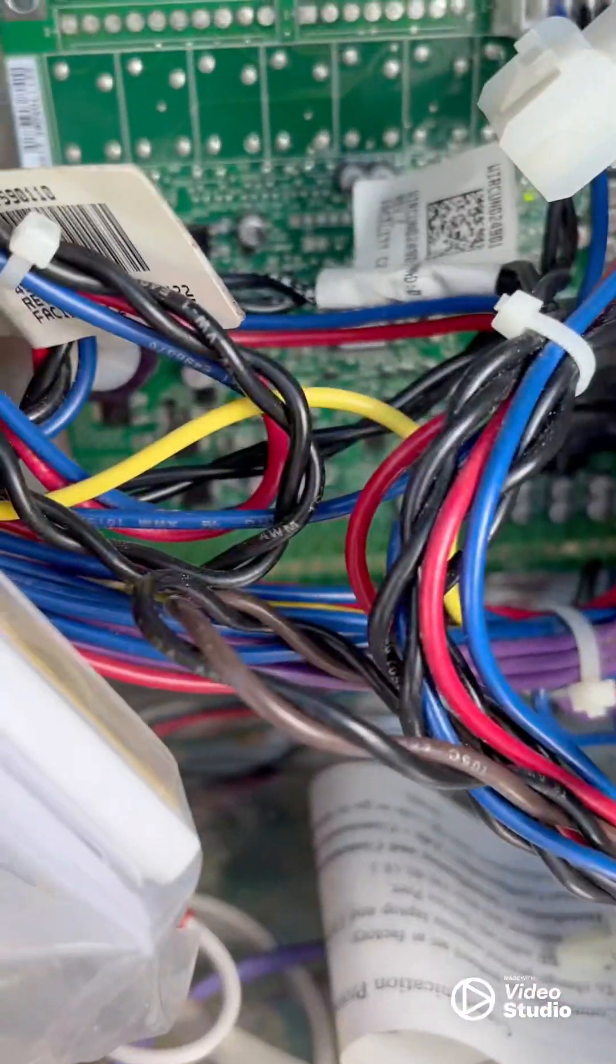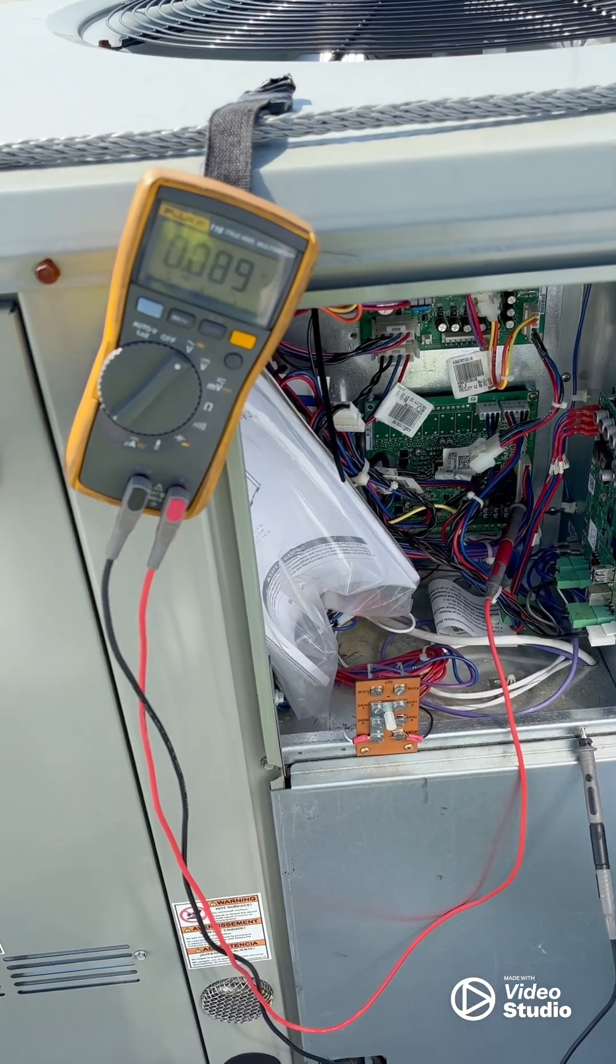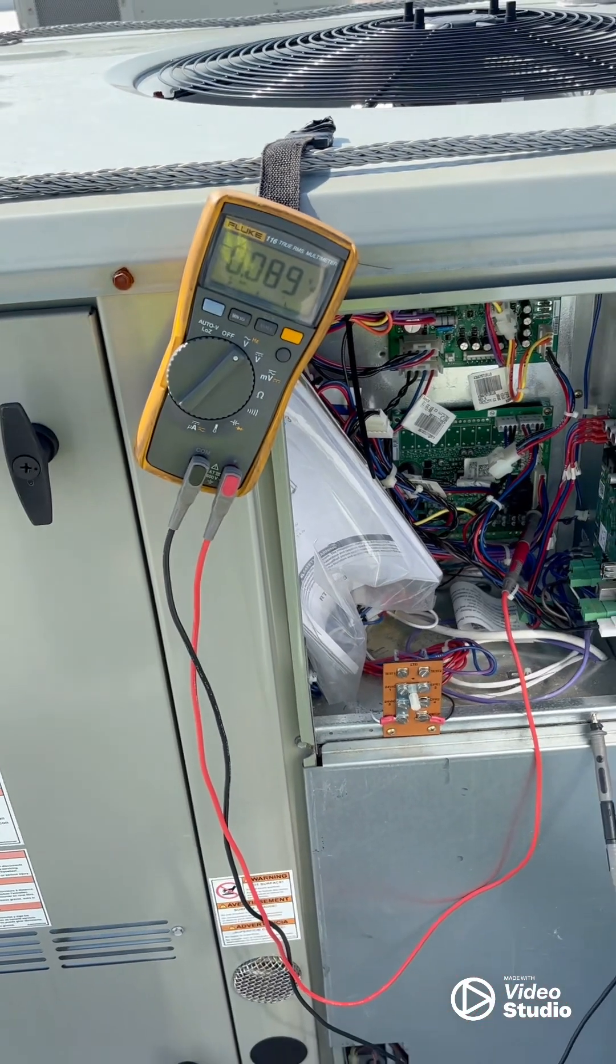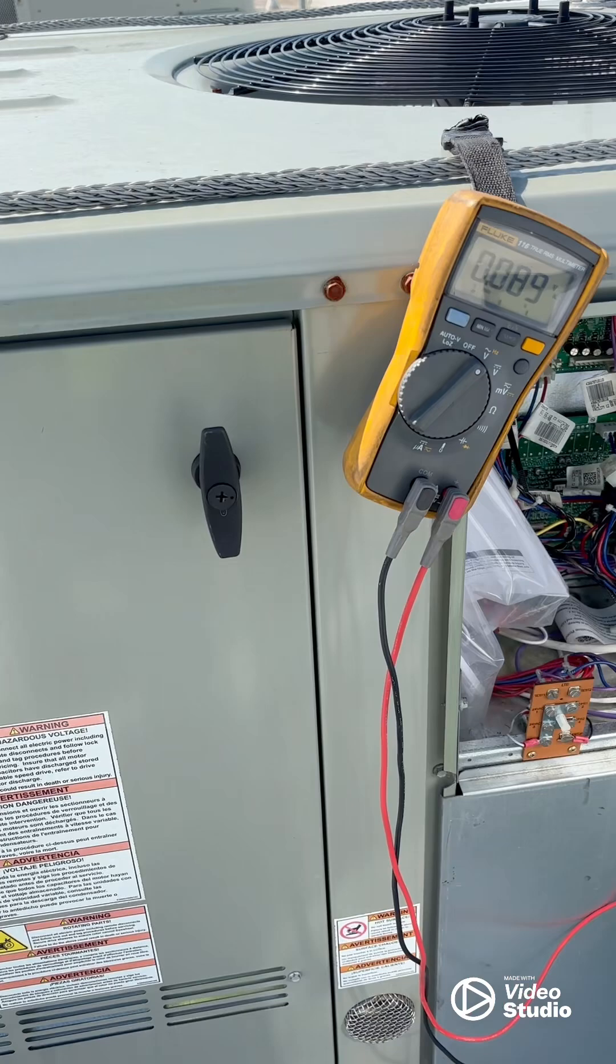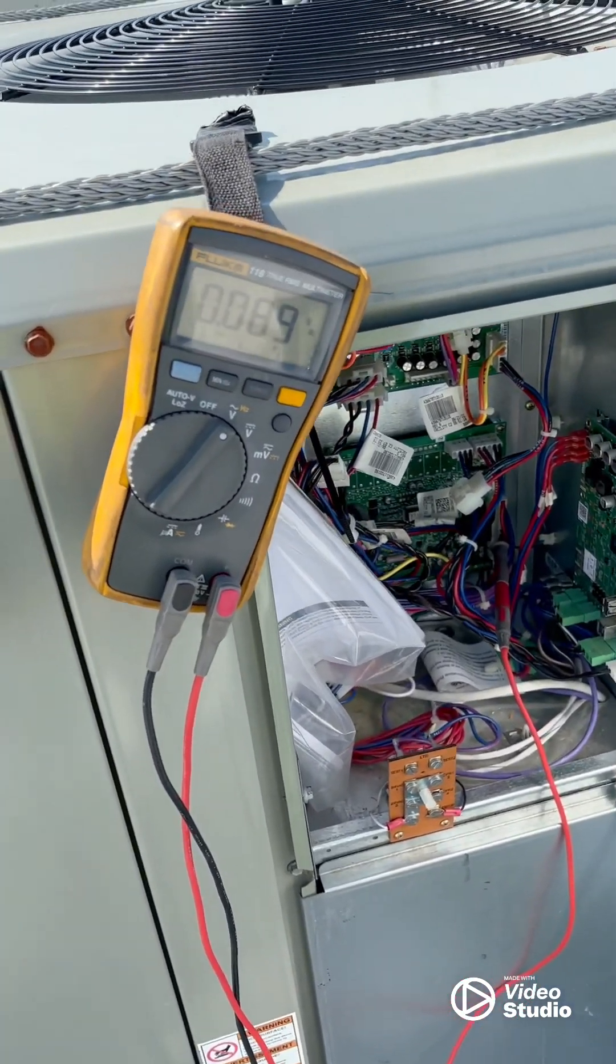So you see I got the blinking LED on the RTRM board. I'm going to show you and confirm that this board is actually bad. I'm supposed to have 24 volts coming out of this board when I put it in test mode.